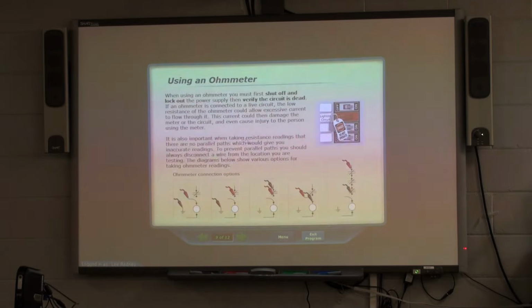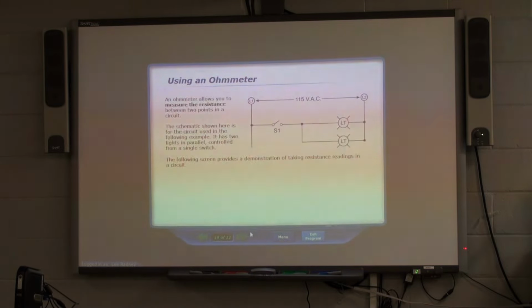It's also important, when taking resistance readings, that there are no parallel paths which give you inaccurate readings. To prevent parallel paths, disconnect the wire from the location you're testing. So when testing different locations, you have to remove a wire to get an accurate reading. If we're reading across contacts, across different places, we take it out of one side of the circuit, so we can safely measure from that. So it allows us to measure resistance. The following screen is going to show us how to do that.